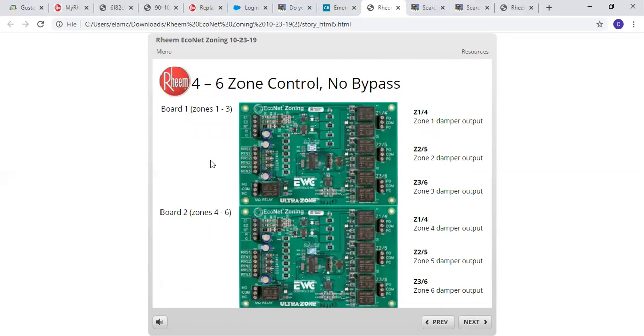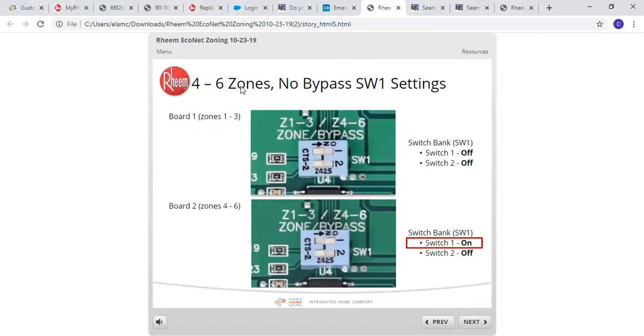Now here we'll get through to zones 4 through 6 with no bypass. So you have zone 1, 2, 3, down here 4, 5, and 6. So if we're going to do 4 to 6 zones, no bypass, SW1. So our boards 1 through 3, there again, our dip switches will be off. If we go down to board 2, 4 through 6, we want to turn dip switch 1 on. We don't have a bypass, but we are using zones 4 through 6. So dip switch 1 on.